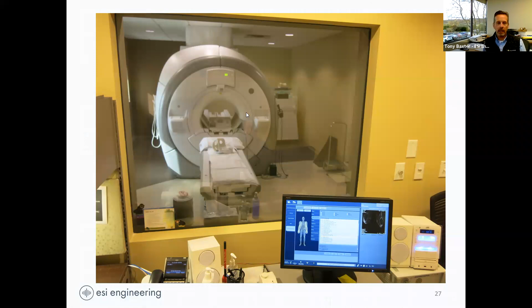A client came to us, an existing hospital, but they wanted to put an addition on. Part of that addition, on the first level, kind of a basement level, was a big mechanical room, and they're putting an MRI in. Of course, they're going to put the MRI above the mechanical room, which is a bad idea, because you've got all this ductwork and piping and pumps and fans. They had big fans hanging from this slab, kind of over in this area. And here you've got a very, very sensitive MRI.